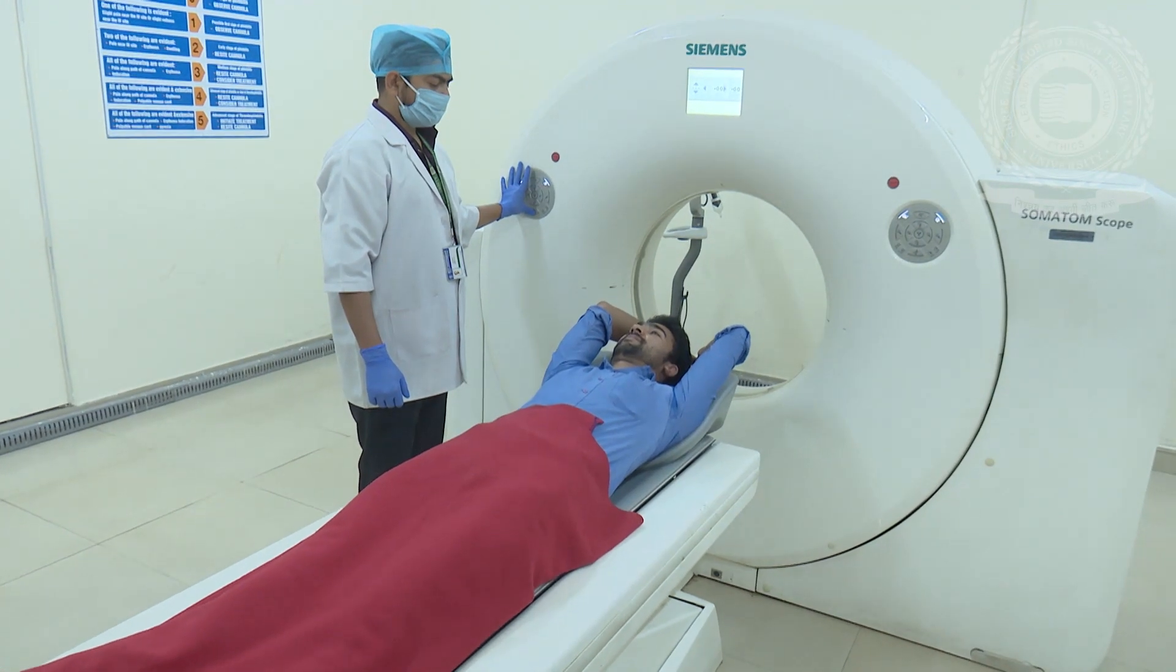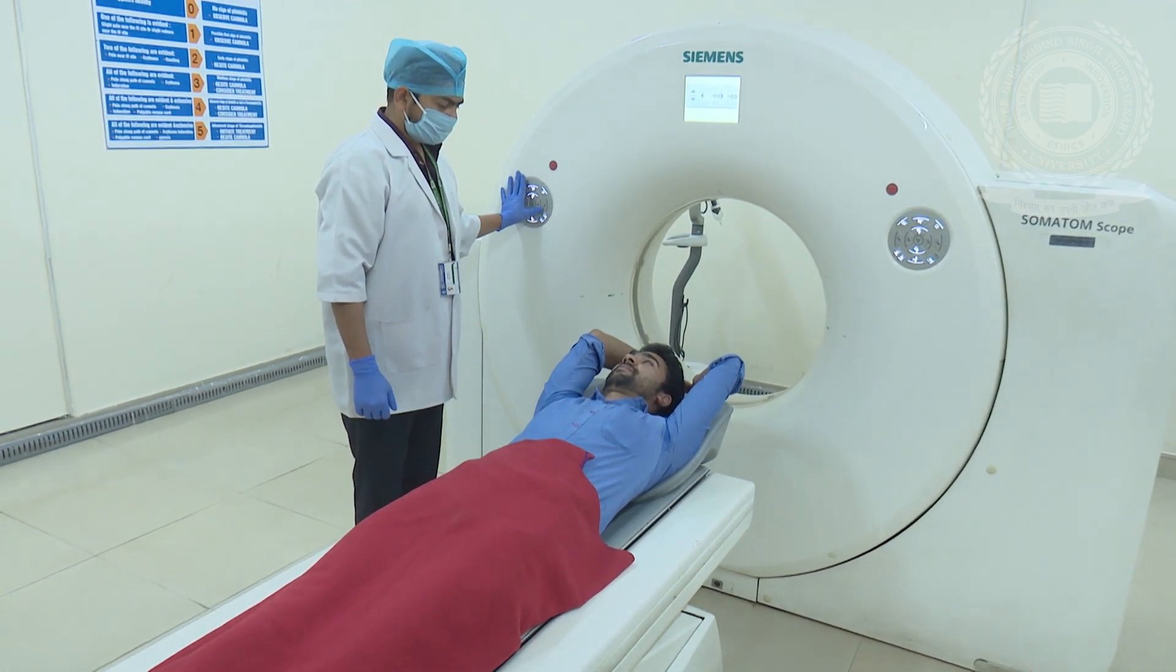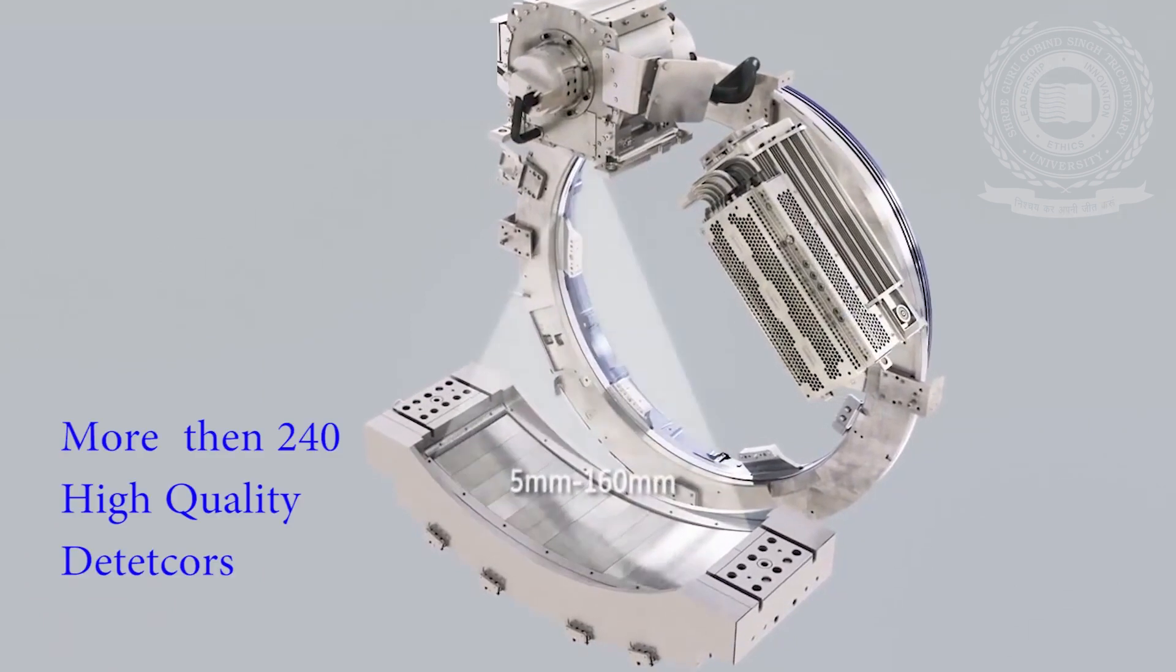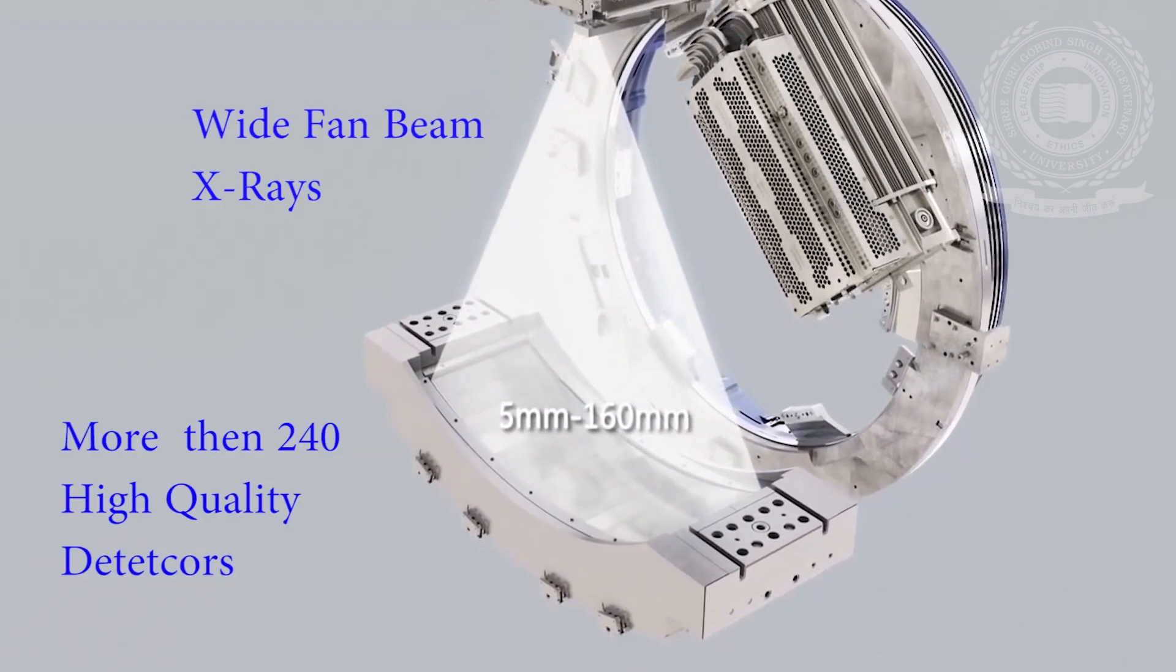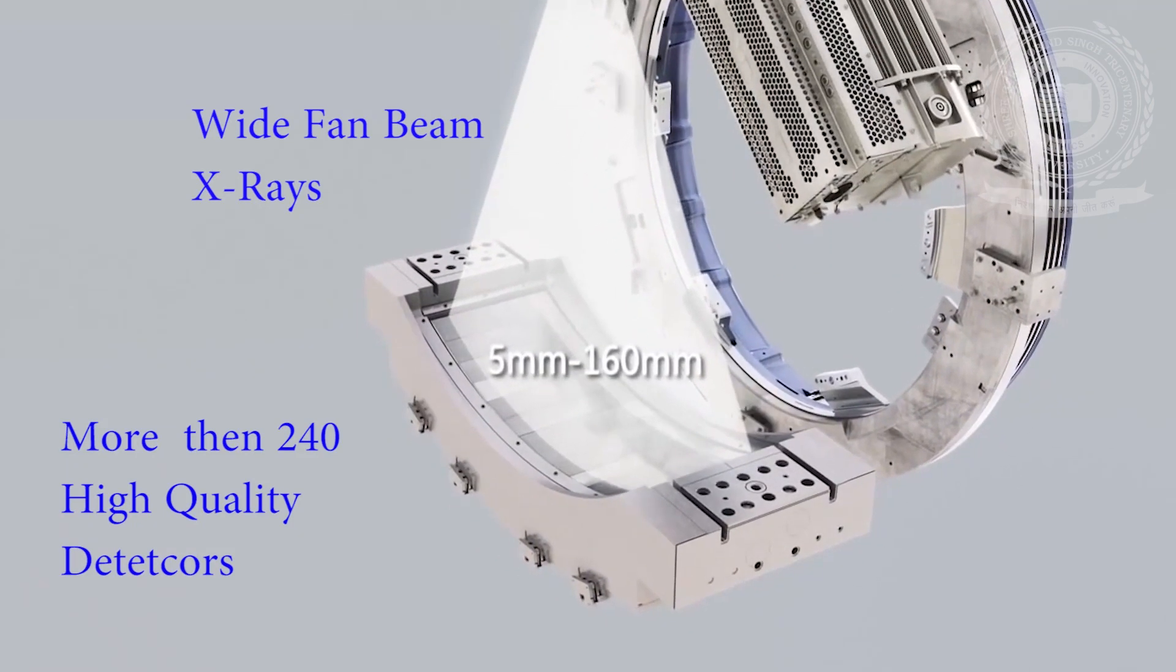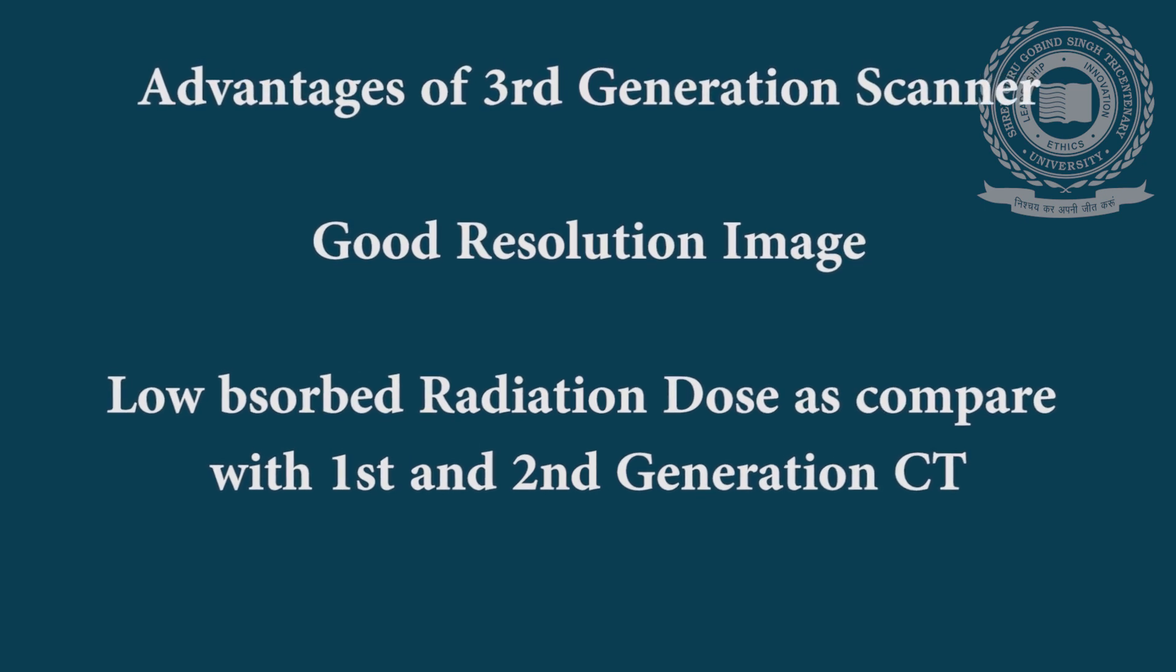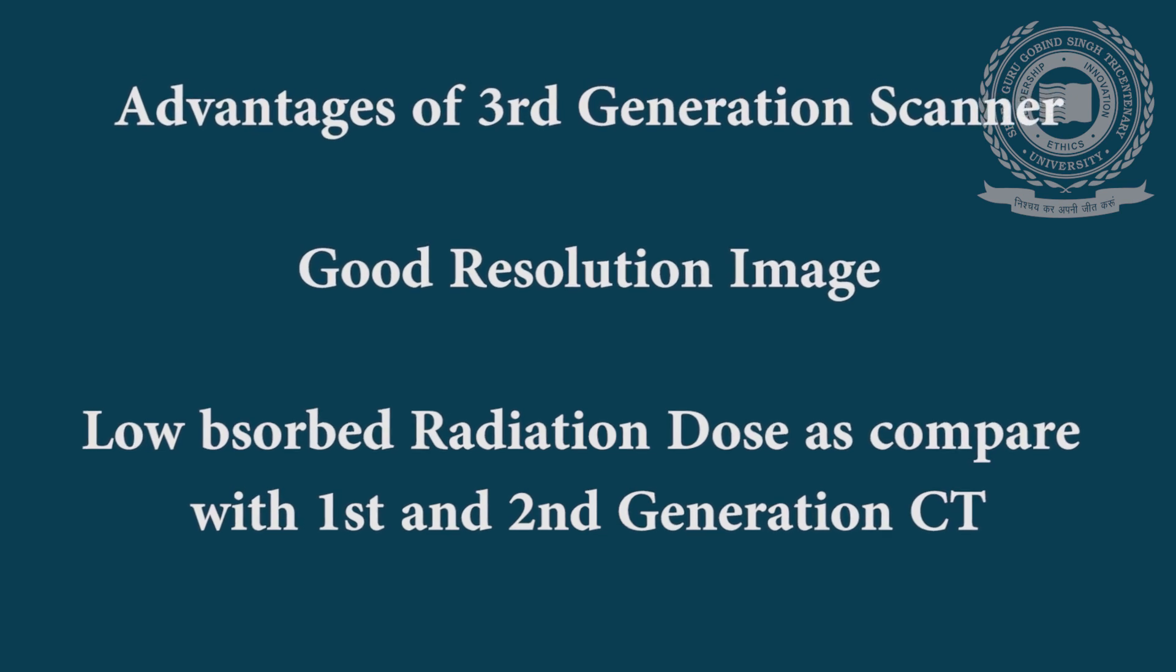Earlier this generation was only meant for single slice acquisition in one 360 degree rotation of X-ray tube, but nowadays it comes with multiple slice acquisition mode in one rotation of X-ray tube and detectors. Later on in this generation, 240 high quality detectors were used with wide fan beam of X-rays. More advantages of this equipment were good resolution image quality, low radiation dose in comparison with the first two generations, but still radiation absorbed dose was on the higher side.